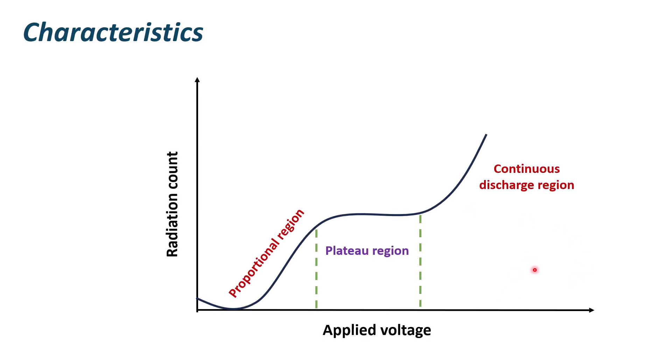The characteristics of GM counter are like this. Characteristics are drawn with respect to applied voltage and generated radiation count. If you see in this diagram, at first, there will not be much amount of increase in the count. Enough voltage should be applied to the tube in order to have working from it. The tube does not function below a certain threshold. At first, the applied voltage is proportional to the number of pulses generated. This region is termed as proportional region.